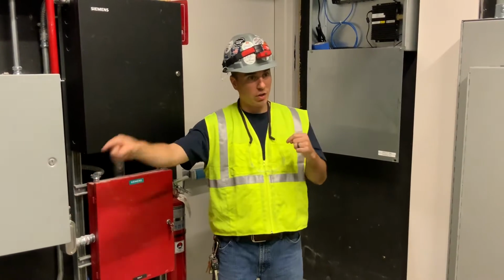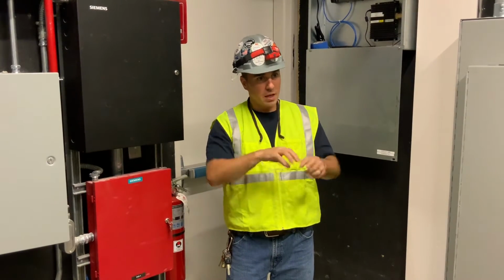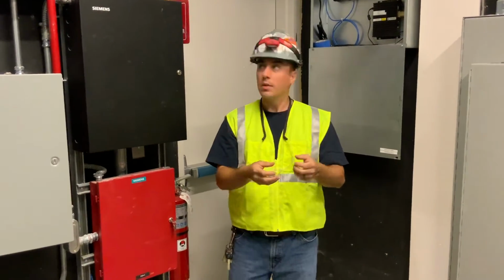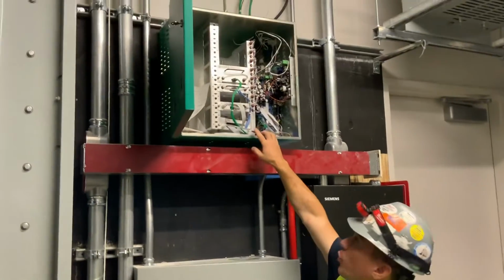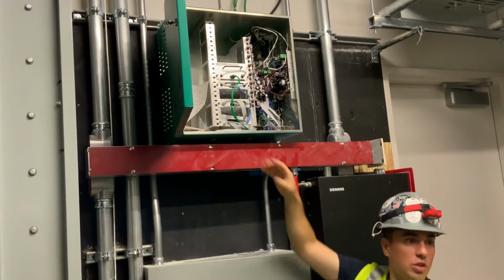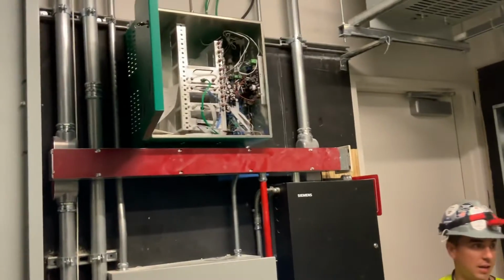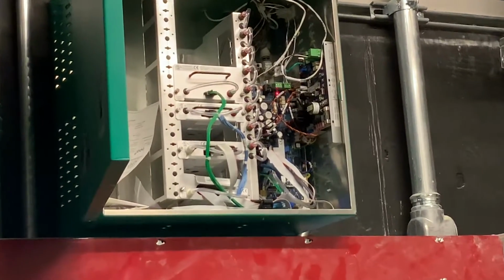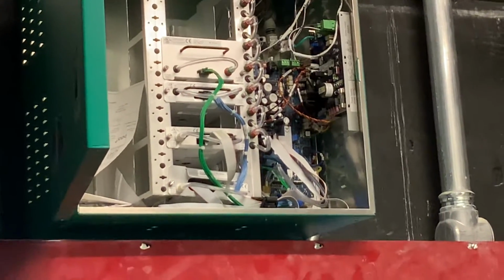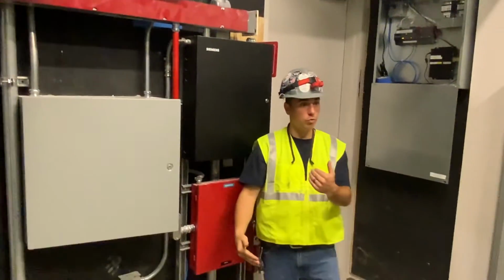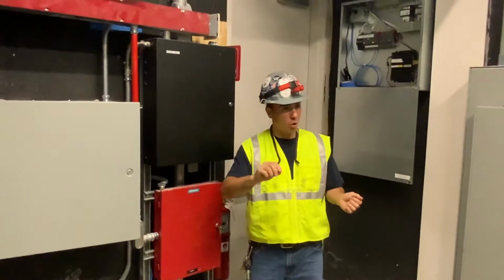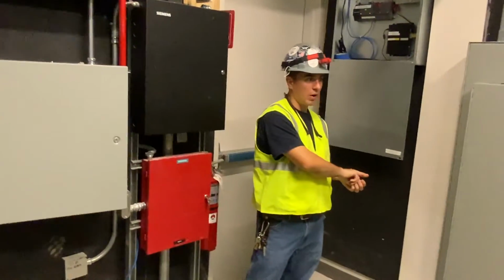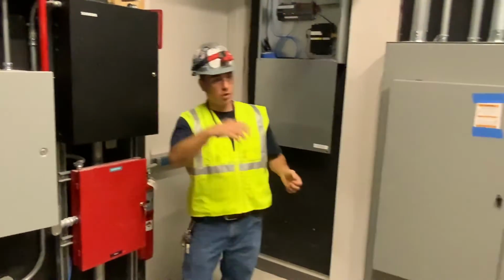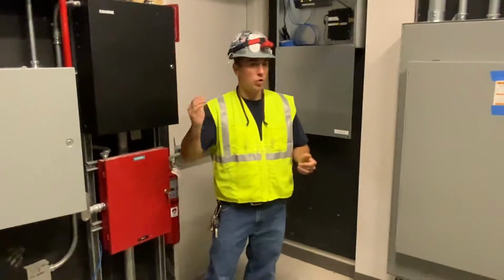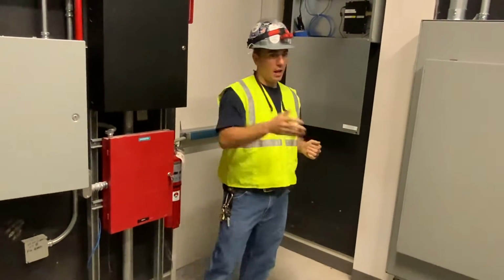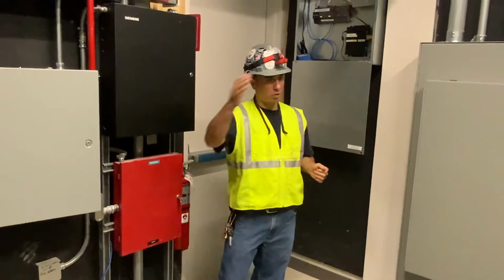Once it's now cleared out the old air that was in that line, it switches over to a low flow mode, and it runs that packet of air through these series of sensors. And those sensors sample that air. Once it has the sample, it switches over. The solenoid that was open for room 1 closes down. The solenoid for room 2 opens up. It goes to high flow mode again. It purges that air out of the line again, and now it's going to switch back to sensor mode. So it's constantly going through a cycle and sampling it. Every time it finishes, it starts back at the first one.